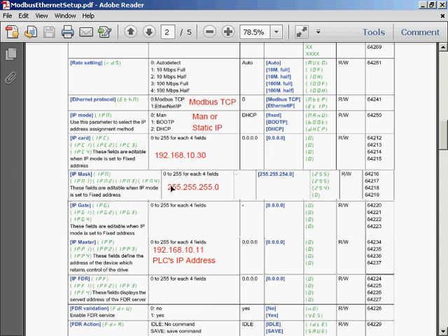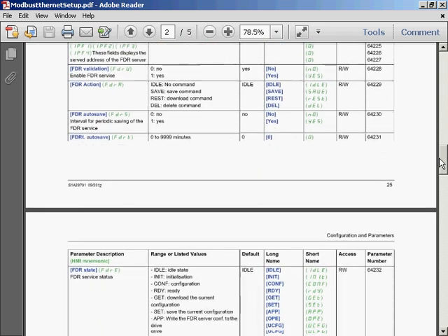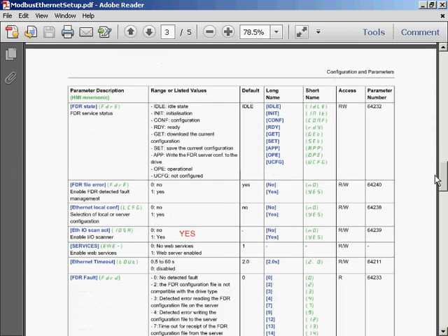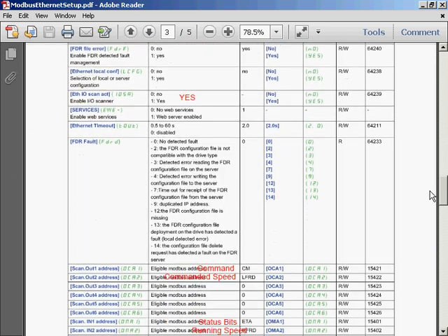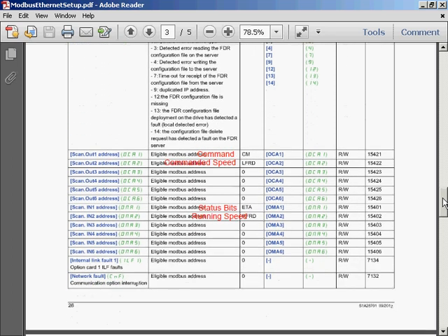And since we're doing Modbus TCP, I am going to configure the PLC, which is the IP master. This 192.168.10.11 is the PLC's IP address. As I scroll down further, we'll look at enabling the I/O scanner. We're going to go ahead and select Yes there. And the default settings for the registers that we're going to control and monitor to command the drive to run and to monitor its current state.